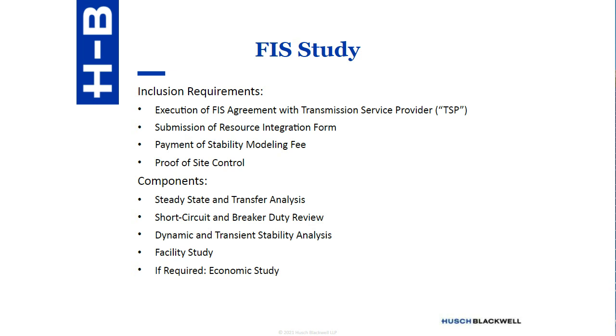Now, the full interconnection study is made up of 4 or sometimes 5 components: the steady state and transfer analysis, a short circuit and breaker duty review, the dynamic and transient stability analysis, and the facility study. The first 3 are looking at the technical engineering ability of the project to interconnect. The 4th one, the facility study, is looking at the physical structures needed to interconnect that need to get built by the transmission service provider, or also by the generator itself. And it also has cost estimates, and these are important because they will ultimately determine what the security will be required for whenever a generation interconnection agreement is eventually executed.